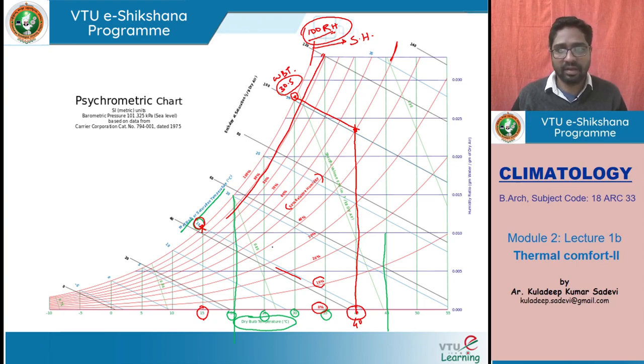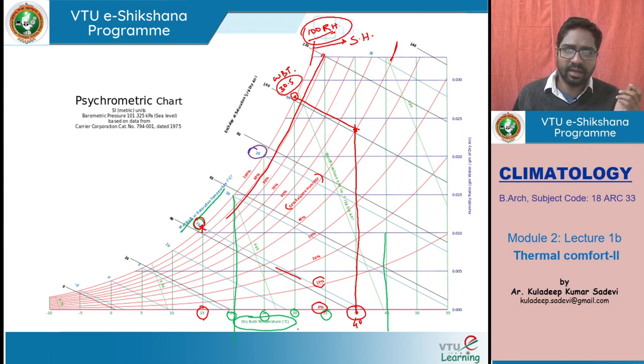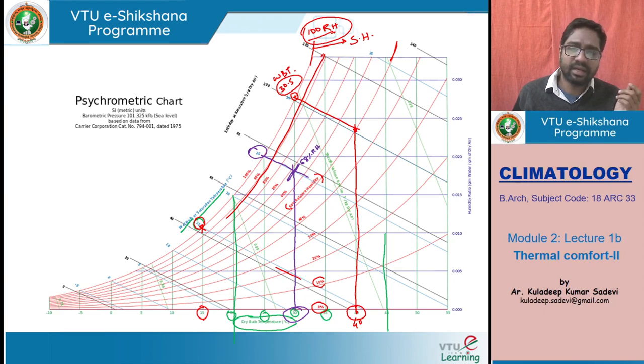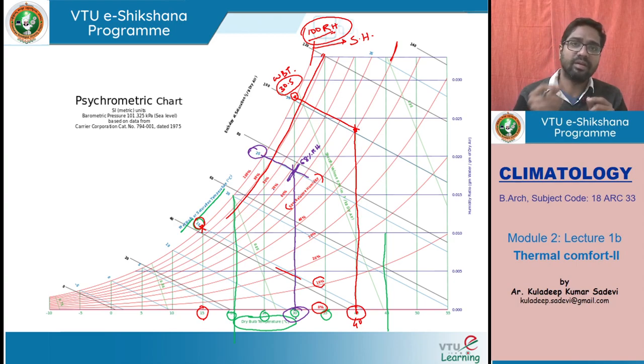Let us do another simple calculation. Say my wet bulb reading is 25 degrees centigrade and dry bulb reading is 30 degrees centigrade. Let us understand what is the RH here. The wet bulb line and dry bulb line, wherever they are meeting, we see where it is hitting the RH curve. This is 60, this is 70 — maybe about 68 percent RH. So at 68 percent RH, if the dry bulb is 30 degrees centigrade, my wet bulb will be roughly about 25 degrees centigrade. This is how we can plot and understand different atmospheric conditions.